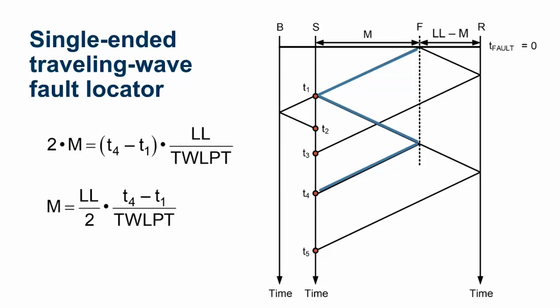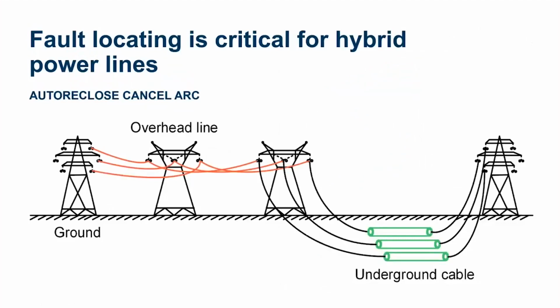So what can we do with all of this? Well, we can perform auto reclose cancel, and this is called ARC if you look at any of our bubble diagrams that show all the different functions that are in the relay. So let's just ignore this underground section for a second. Let's say you've got just this overhead transmission line, and let's say this first part of the transmission line is not in an area that's prone to wildfires. So if you have a fault in this area, you can allow auto reclosing. Since the traveling wave fault location is extremely accurate, you can tell the relay, if I have a fault in this first section of line, I'm going to allow my auto reclosing to take place.